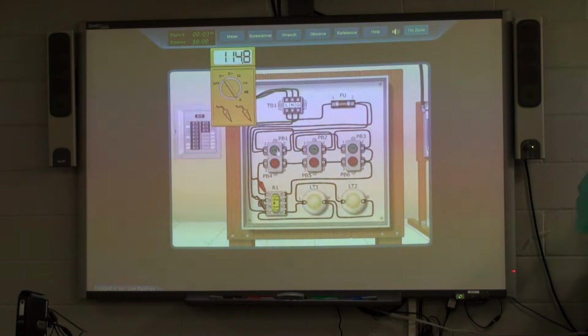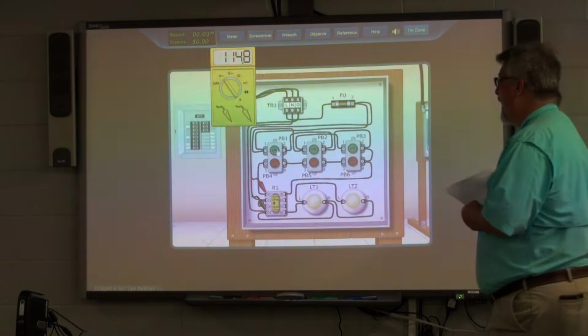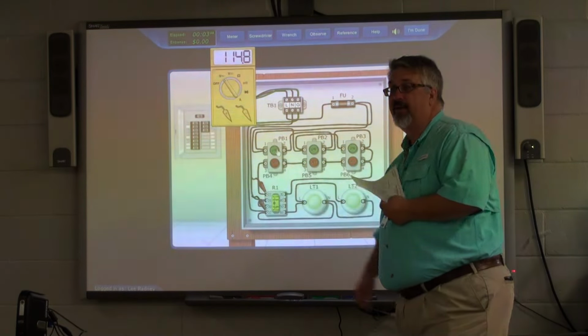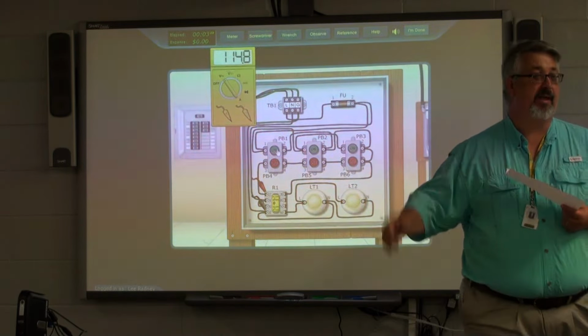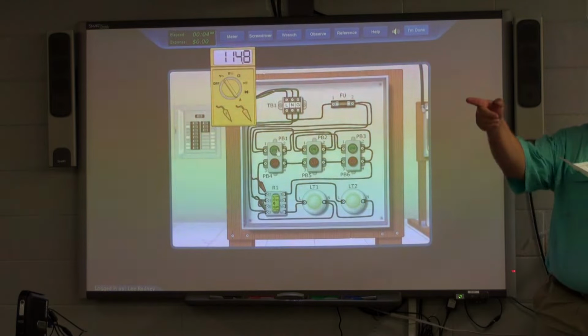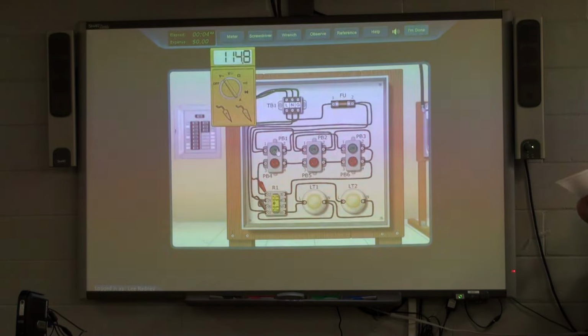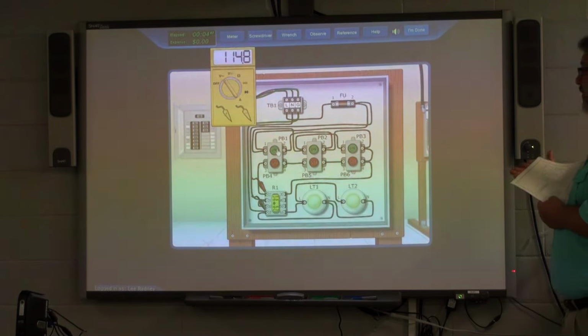You gotta transfer the voltage. All right, so sure enough, 114.8, some mild line losses. We see the indicator that our coil is energized, approximately 115 volts. I did that for y'all. 114.8, so our coil is energized.